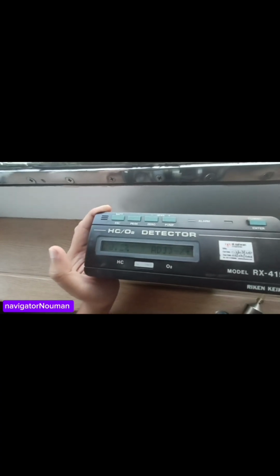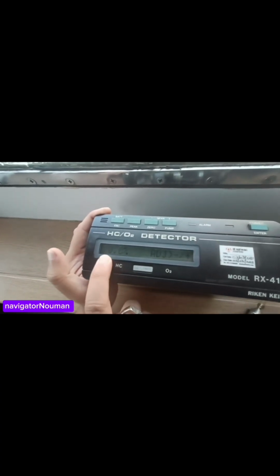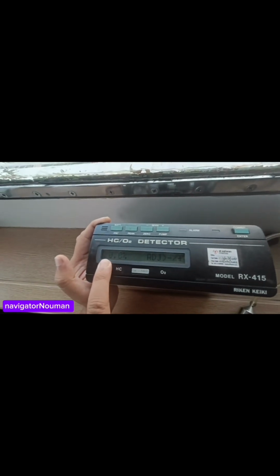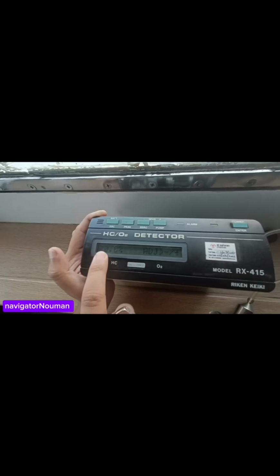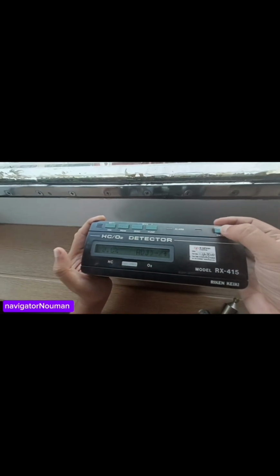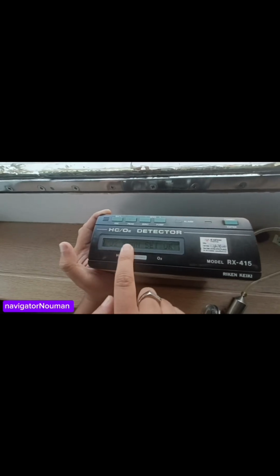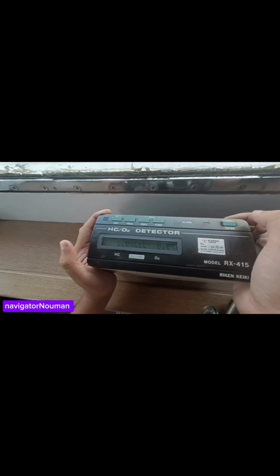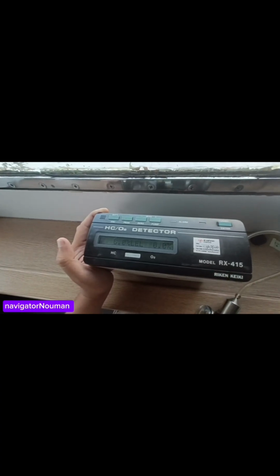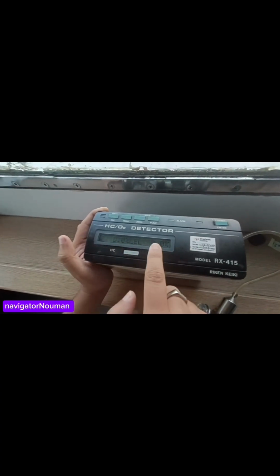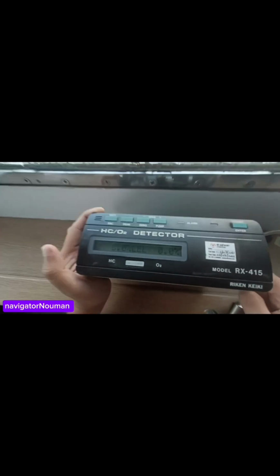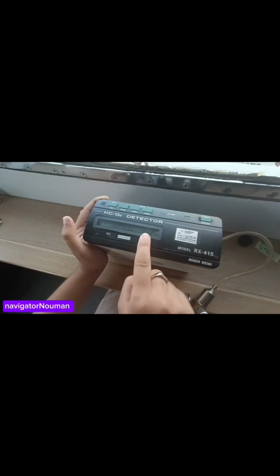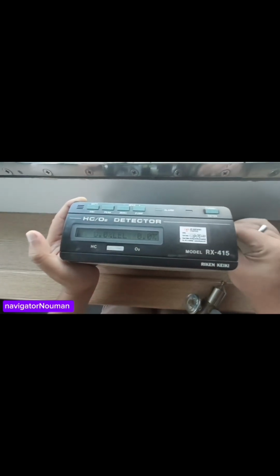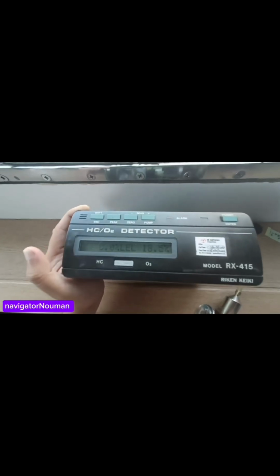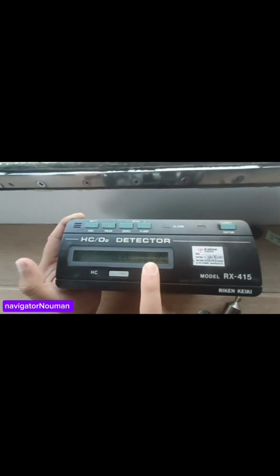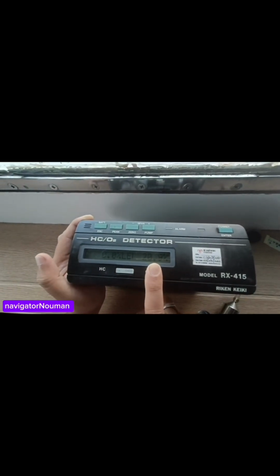It's reducing and it came down to 0. Whatever gas is inside the bottle, it is showing here. That means our equipment is showing the actual reading. Then we will press the enter button and our O2 span set is okay. Friends, this was the calibration of O2. Now you can see 0% LEL here and 0% oxygen because the hose is connected. As soon as I remove the hose, it will show the atmospheric oxygen. So I am removing the hose now. As soon as I remove it, it will show the atmospheric oxygen, 20.9. Friends, this was the calibration of the Tankscope.